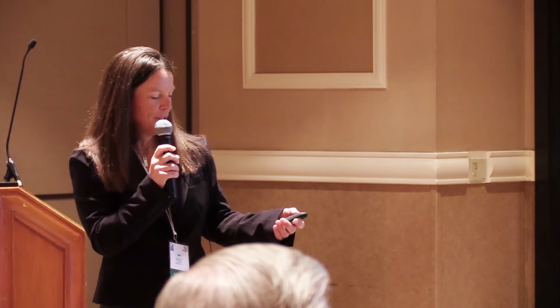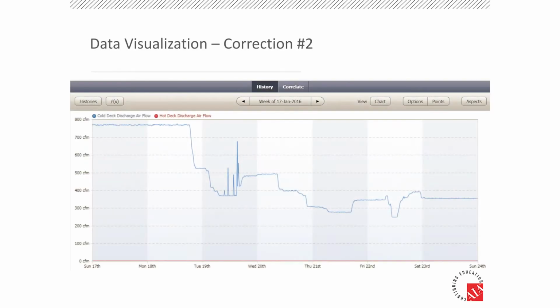So they went back to the drawing board, and on January 17th they deployed yet another program in that laboratory controller. Now you can see how the system is performing: our hot deck airflow is still shut off, and the cold deck airflow is modulating slightly, probably in response to occupancy and nighttime load, and we're down at 300 CFM instead of 800 CFM.